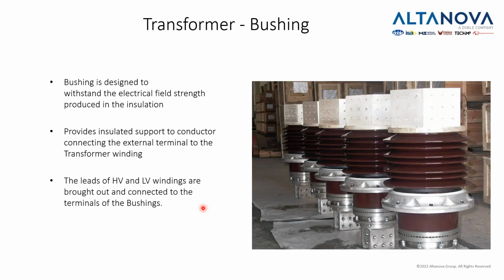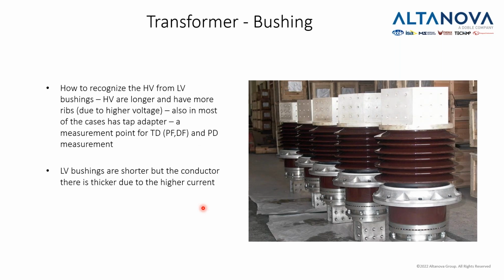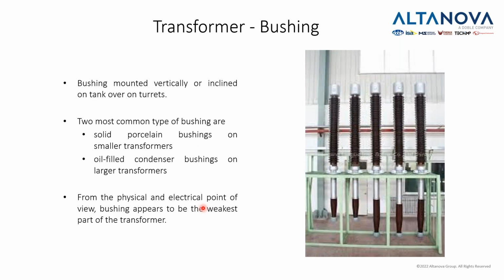Apart from the tank, we have bushings. A bushing is designed to withstand a very big electrical field, because the bushing is kind of an interface between the transformer and the outside world. And apart from the on-load tap changer, the bushing is also very much prone to defects, because it needs to sustain very, very high fields, since it's basically bringing high voltage into the transformer. You can always tell the difference between the high and the low voltage bushings, because the high voltage bushings are physically bigger than the low voltage bushings, and in a transmission transformer they will be much further apart from each other.